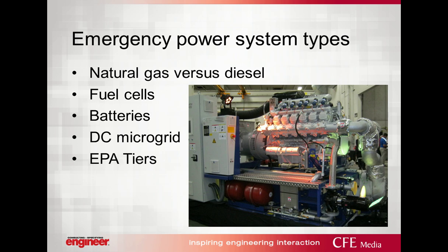Now, we can't talk about natural gas versus diesel without mentioning the EPA. Tier 4 is the most stringent requirement for generator sets, whether it's diesel or natural gas, and the requirements are different for each one of those. While an entire presentation can be given on Tier 4, the primary takeaway is that the more popular Tier 2 classification cannot be used for financial gain for peak shaving contracts with a local utility.